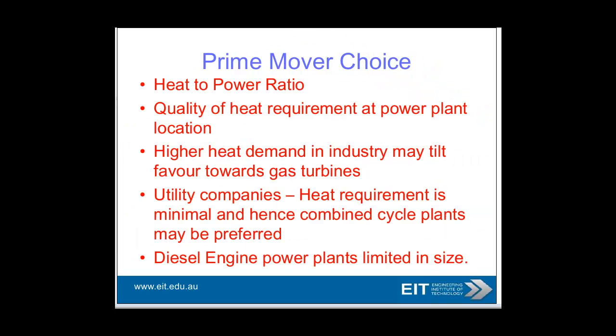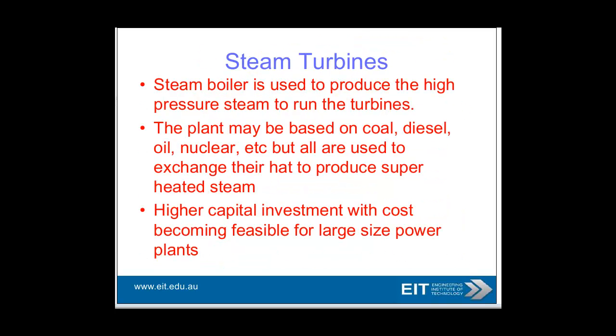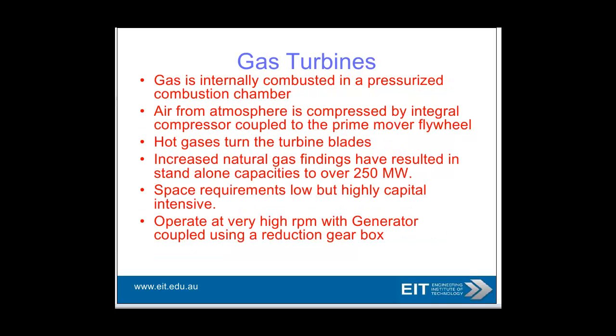Prime mover choice is related to heat to power ratio, and higher heat demand may tilt you in favor of gas turbines. For utility companies, heat requirements are minimal, so you may find combined cycle plants preferred. Obviously diesel power plants are limited in size. Steam turbines use a steam boiler, and the plant may be based on coal, diesel or nuclear. Obviously nuclear is restricted to certain countries.